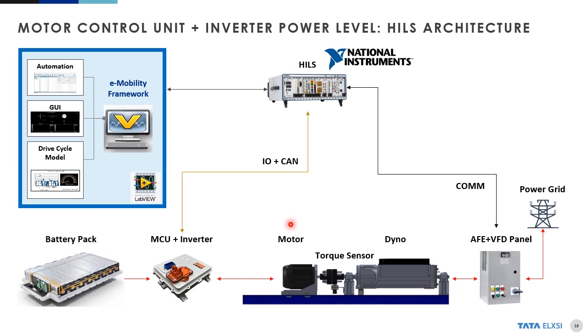So it will give a required loading torque value as an input to the VFD. The VFD converts this to a current value and devises the control strategy of the dyno so that specific current can be generated from the dyno when it acts as a generator.